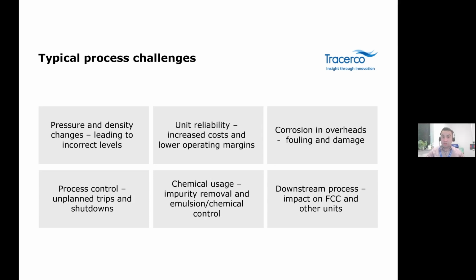Thank you very much. So typical process challenges. What are the main challenges we see when we're talking to our customers? Changes in the process condition which lead to offset or incorrect level output, potentially bringing the trips in at the wrong point. Reduced reliability with a high amount of plant shutdowns, all impacting our operating cost and reduced outputs. Physical damage to the plant caused by corrosion and fouling. High amounts of chemical usage to improve purity and emulsion control, such as demulsifiers and anti-foam agents. The downstream process may receive process and fluids out of spec.